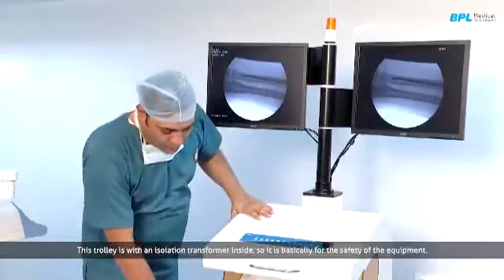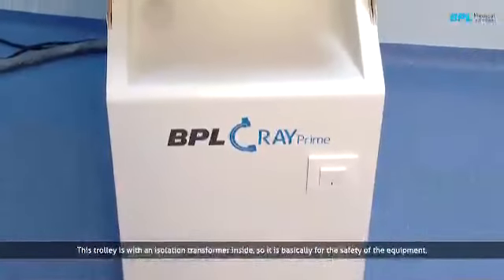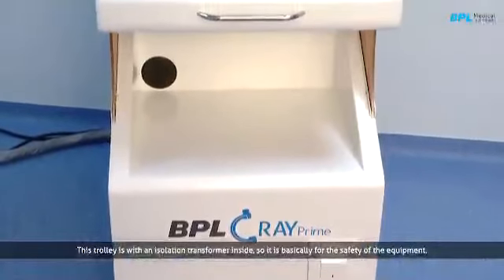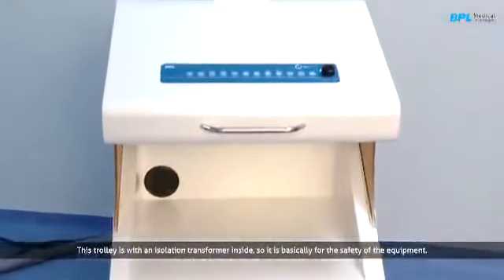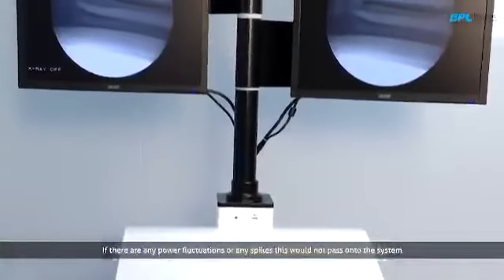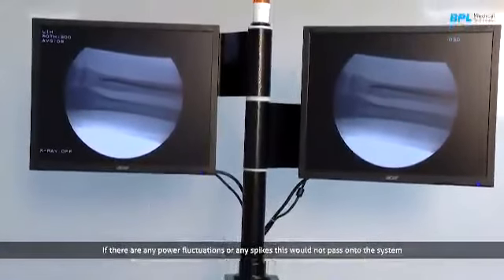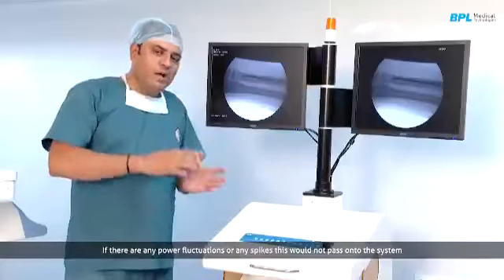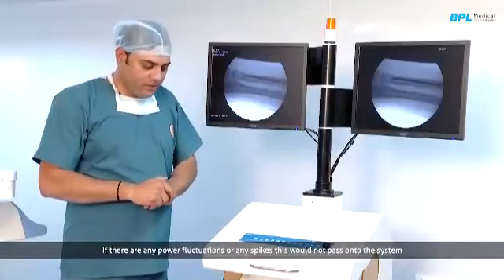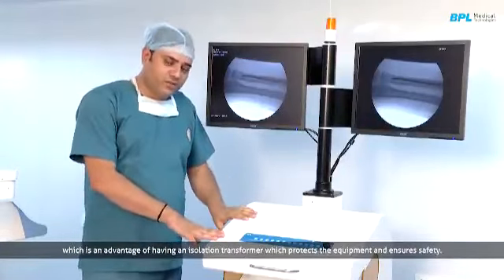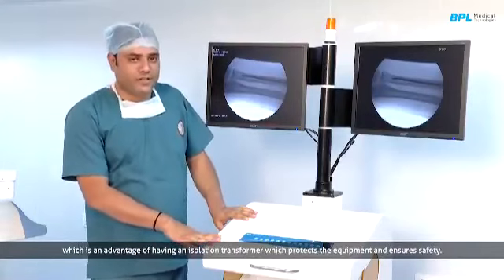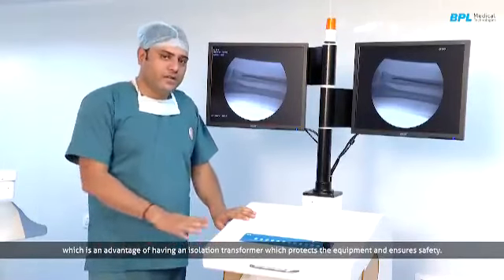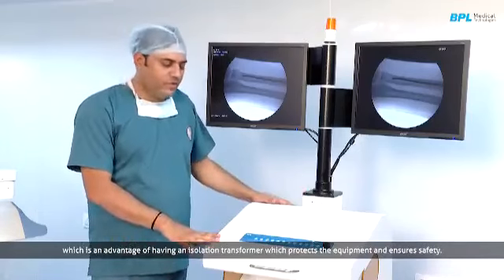This trolley houses an isolation transformer inside. It is basically for the safety of the equipment. If there is any power fluctuation on the input side or any spike comes, it won't pass to the system, and that is the advantage of having an isolation transformer for equipment safety from input fluctuation.